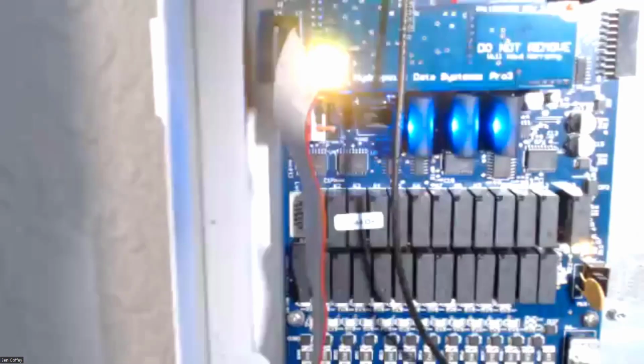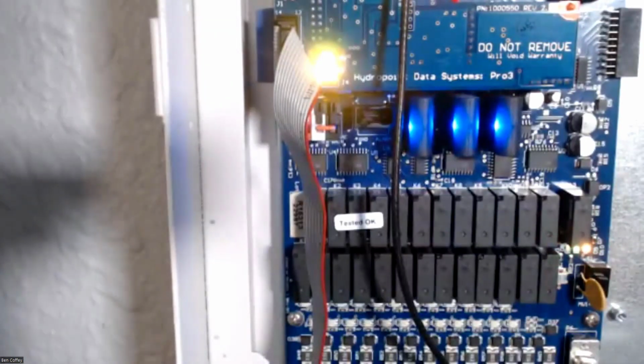One thing I'd like to point out, Ben, can you energize the master valve now that we're on flow sensors? Sure, let me go turn that on real fast. You'll notice the blue LED light, right where the red flashing light, the green, and the amber light is. We'll see a little blue light come on here shortly once Ben energizes the master valve.